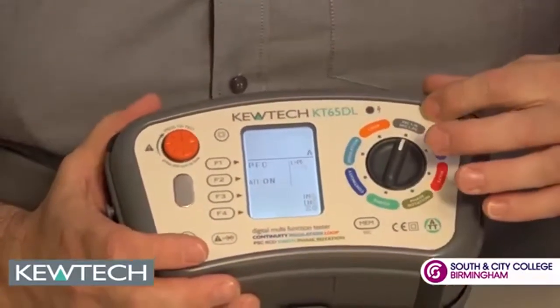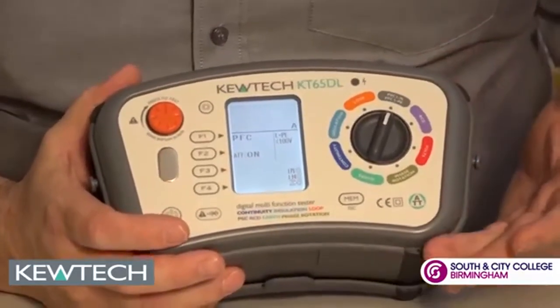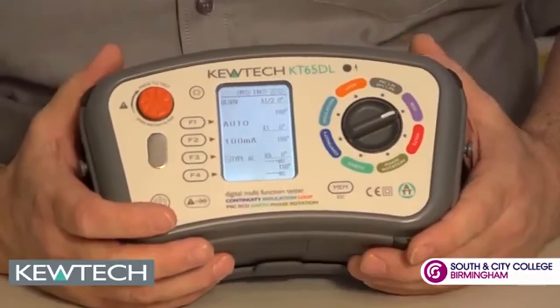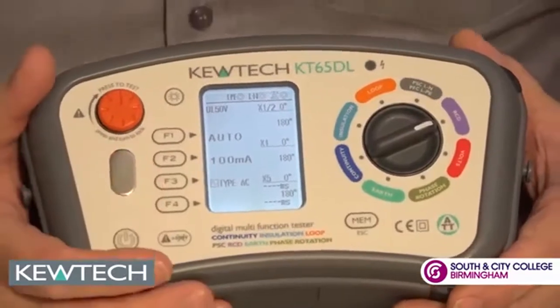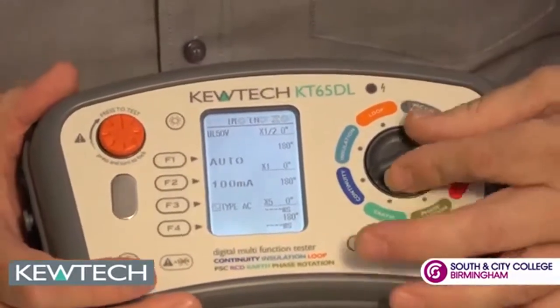Moving around to the fault current testing, this will do single phase as well as phase to phase testing without damaging the instruments. The RCD range is between 10 milliamps and a thousand milliamps — it doesn't matter whether it's a type G or a type S, this can do it all. In auto mode all the results will be displayed on the one screen, no need to scroll through.